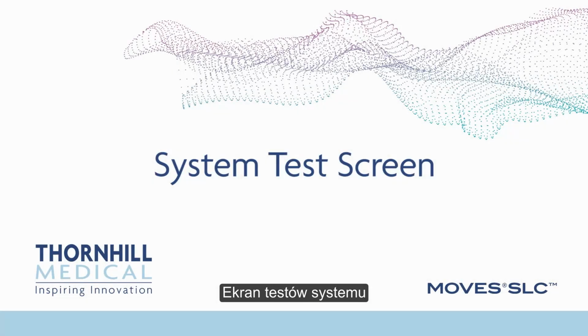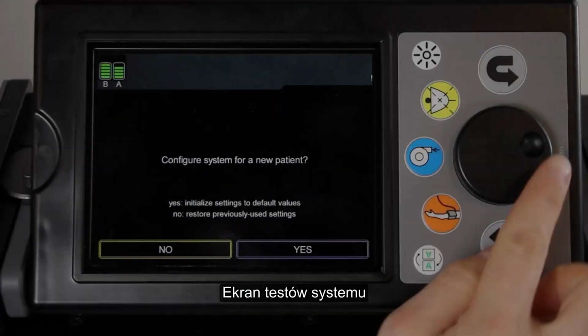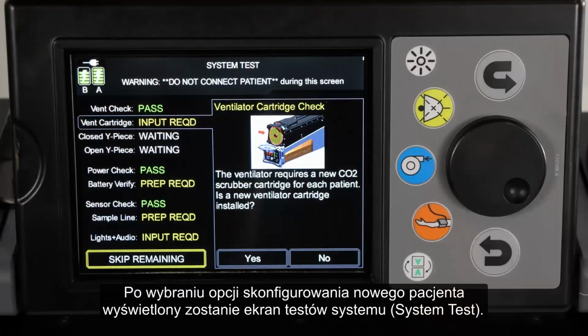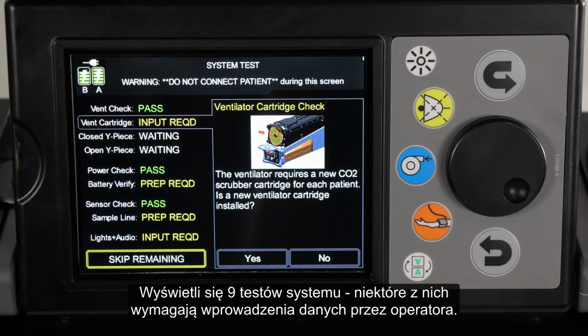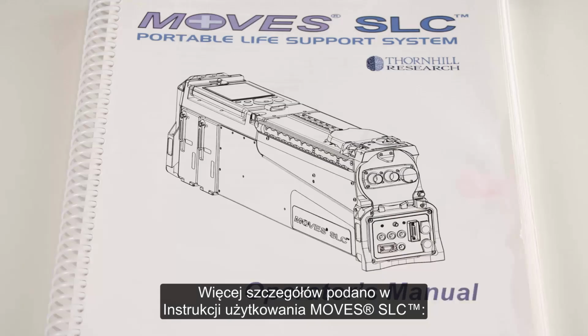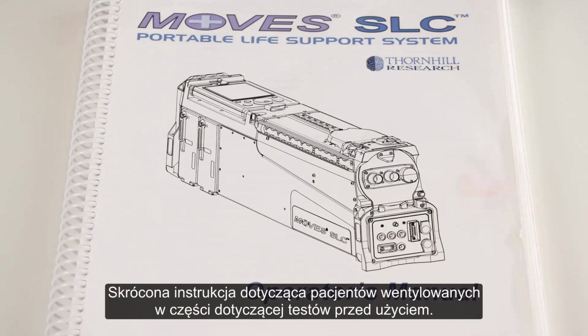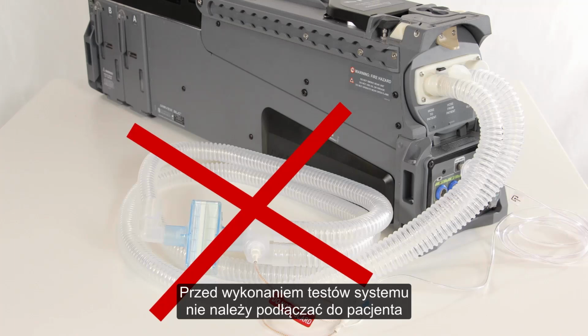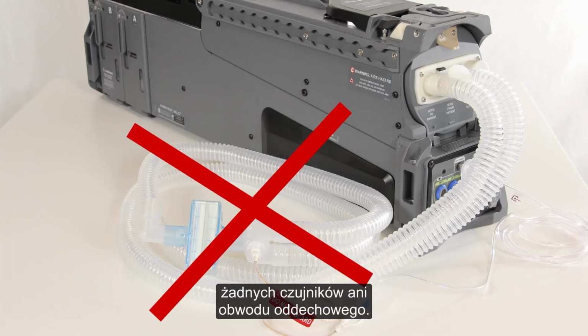System test screen. After you have chosen to configure a new patient, the system test screen is displayed. You are presented with 9 system checks, some of which require operator input. For further detail, refer to the Moves SLC Operator's Manual, Quick Start Guide for Ventilated Patients, in the Pre-Use Test Instructions section. Do not connect any sensors or the breathing circuit to the patient prior to performing system tests.